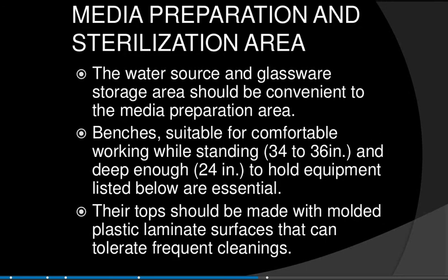The media preparation and sterilization area specification is as follows. The water source and glassware storage area should be convenient to the media preparation area. Benches suitable for comfortable working while standing, 34 to 36 inches high, and deep enough, 24 inches, to hold the equipment listed below are essential. Their tops should be made with molded plastic laminate surfaces that can tolerate frequent cleaning.